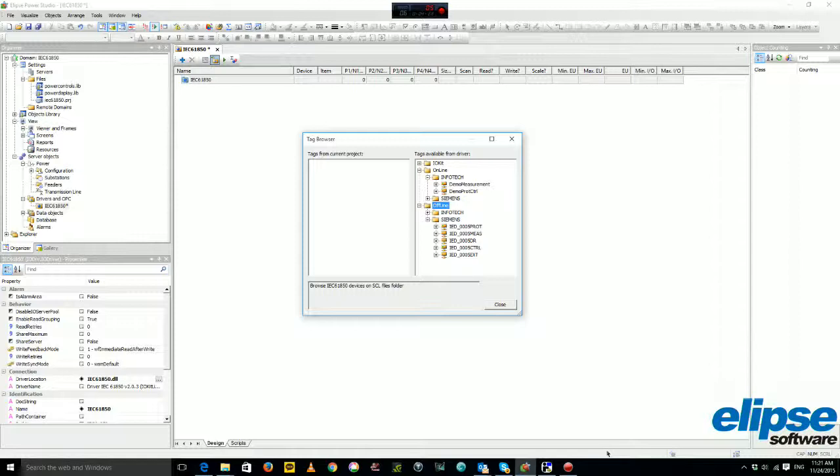If I click on the Siemens here, then I will have the waiting cursor of my mouse, and then I will have an error message, but this is normal because this IED is not online, so this is why I have the error message here. If you see this error message, it probably means that the IED is not connected, or you have a problem with the LD path.